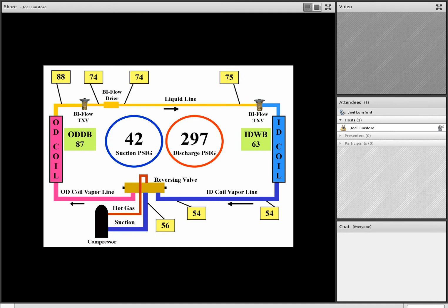Well, the liquid line, we see we have a 1 degree temperature difference across the liquid line with our two temperature blocks, 74 and 75. We see that we have no temperature difference between the biflow filter dryer. They're both 74 degrees. But now hang on a second. Look at the temperature difference leaving the outdoor coil and entering the biflow dryer. We see that we have 88 degrees and 74 degrees.